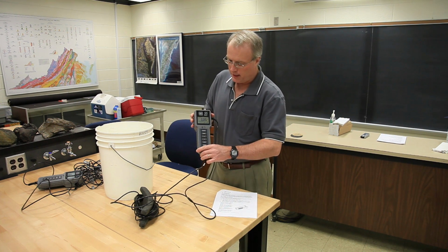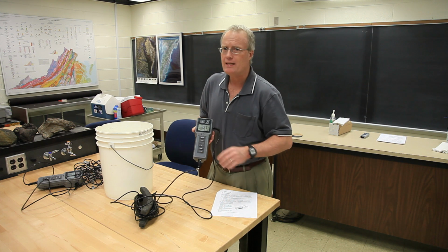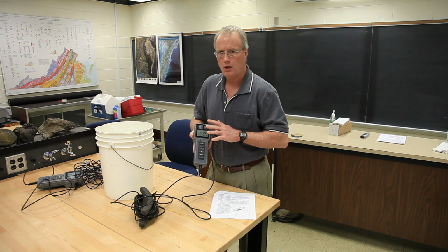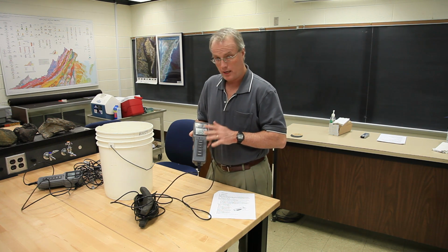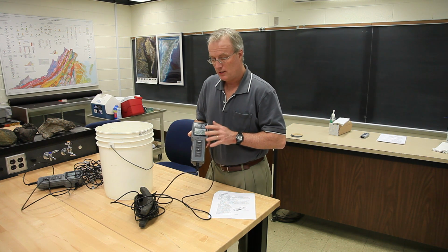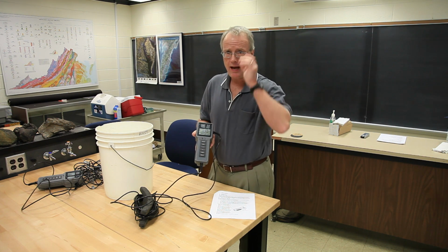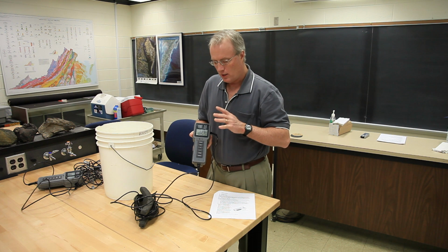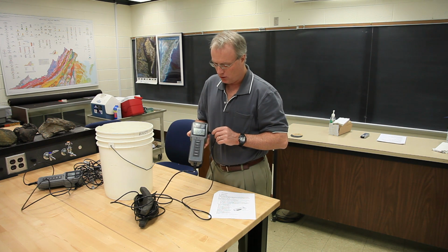First of all, the meter has to be turned on for a good 15 minutes before you can ever start to calibrate it or take measurements with it. So that means you need to remember to turn it on before you leave the lab so that by the time you get to your site, it's ready to go through the calibration procedure.